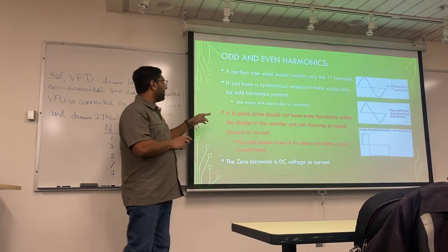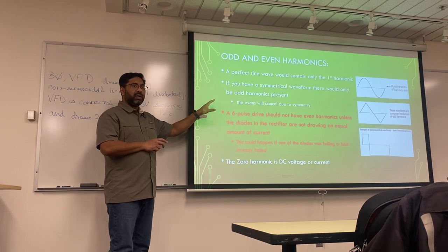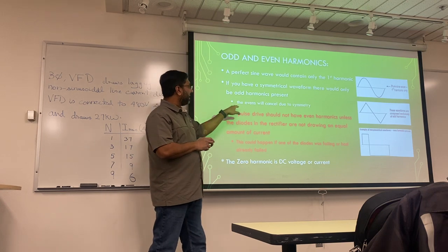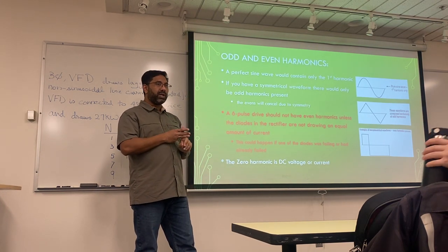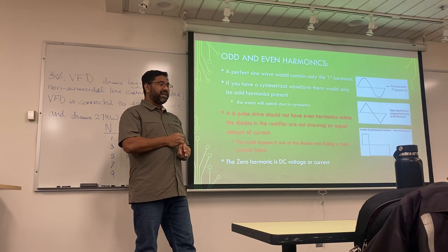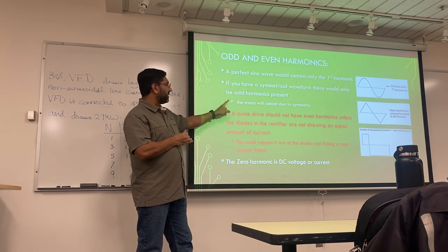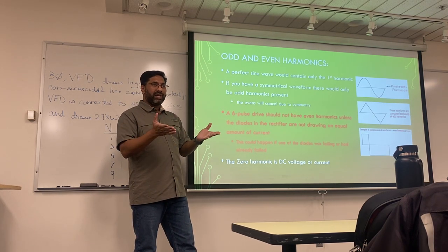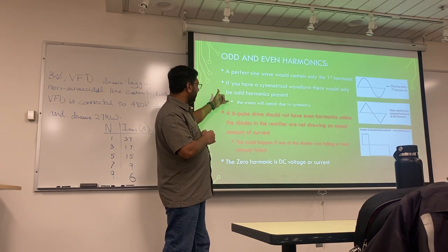Now, this is a bummer, and I still wanted to have it here. Depending on the textbook, they will still tell you the even ones will cancel due to symmetry. That is true only for 3-phase. So at your home, where you have a 120 and a 240 coming in, this is not true. But when we are training up our technicians, we are dealing with 3-phase power, industrial loads, and that's the only reason that it was there.